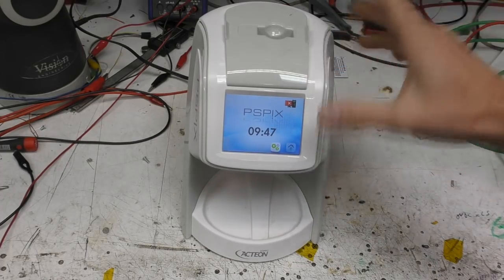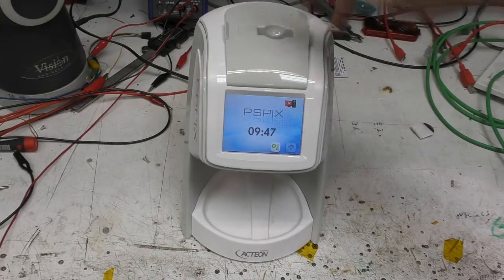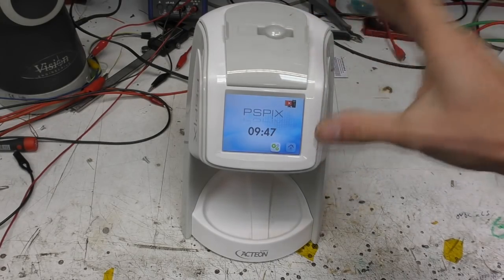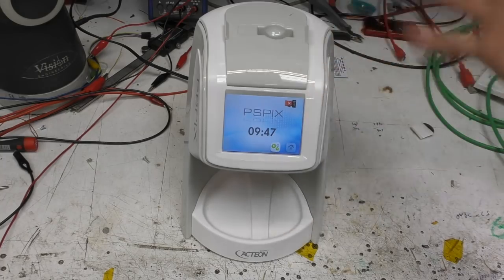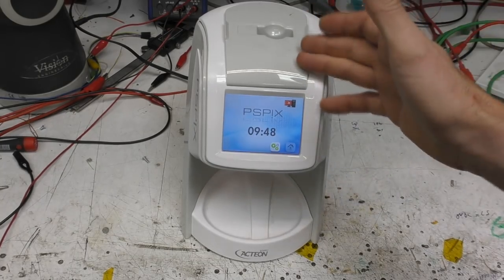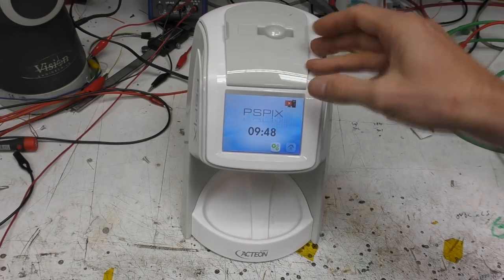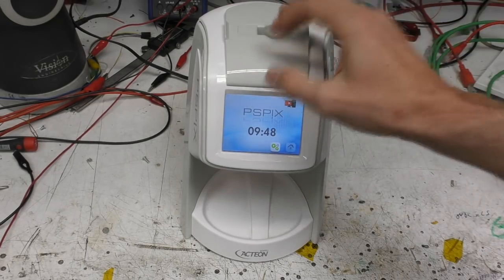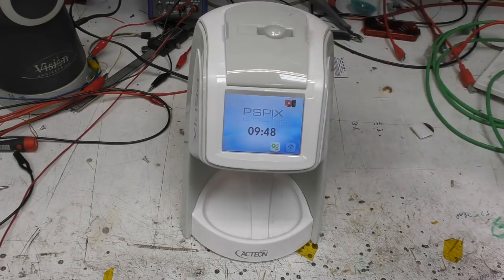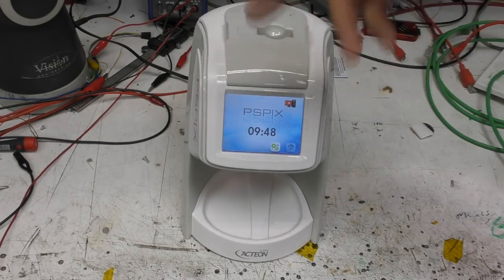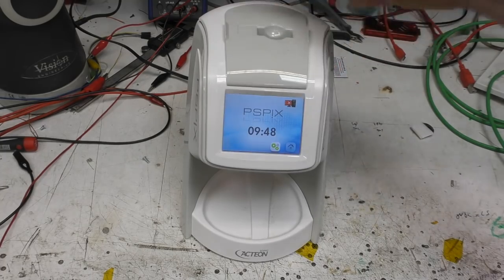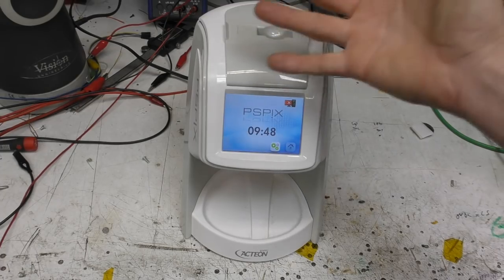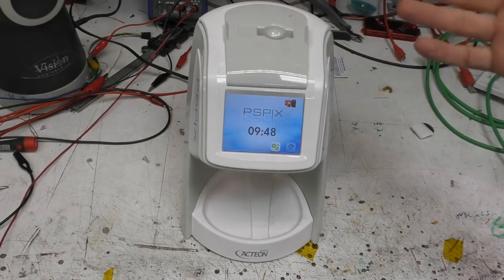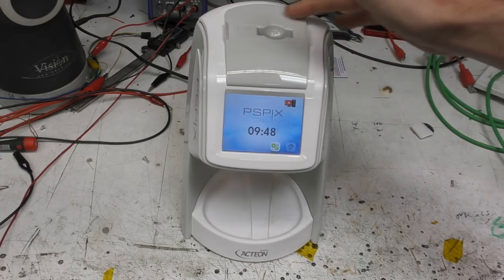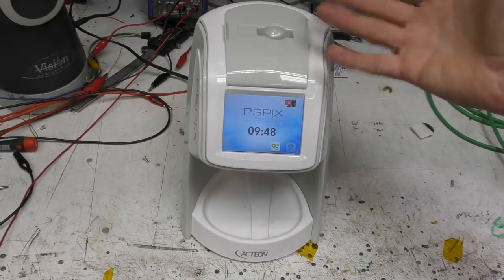Now when I first got it, I was really busy, so I just sort of put it to one side and I thought it was maybe just an optical scanner for film x-rays, but it's not. It's a phosphor type system, which is a sort of intermediate between the old film type x-rays and fully digital x-ray systems, whereby the plate, which is actually illuminated with the x-rays, has got a special phosphor on it, which produces a latent image. Then it gets developed by this unit by scanning it with a particular wavelength of laser and then looking at the light that it gives out, and that depends on how much x-rays it received during the exposure time. So you've got the advantage over conventional x-rays in that it's very, very quick developing.